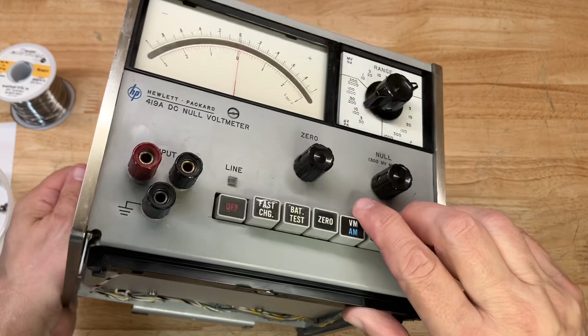Although a lot of this stuff is high impedance circuitry, you shouldn't really be handling it with your fingers, because the oils from your fingertips can actually contaminate some of these high impedance areas and cause inaccuracies in the instrument. So it's best to use gloves when you're working on that kind of stuff. Use rubber gloves or something, or only touch the metal parts of the instrument, not the high impedance portions of the instrument.